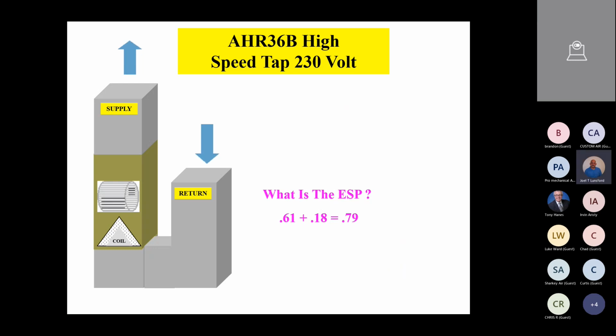Now, fellas, you're going to notice something as you take a look at the airflow charts. You're going to notice that we start getting into some gray areas. When I say gray areas, the chart may run out at like 0.8 or 0.7 based on the chart you're looking at. Some charts go up to 1.0. So based on the product you're looking at, we see that 0.79 on this particular chart, we're crowding the end of the chart. We may even be off the chart. And so it's important that we note that if we have this type of static pressure, we have some issues with the ductwork.